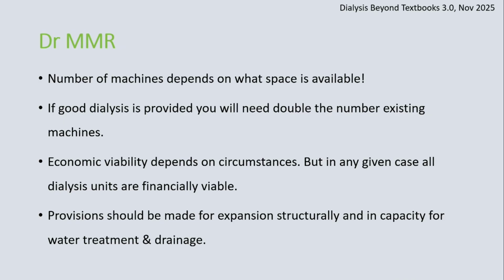Provisions to be made for expansion: when you're starting from zero, you can consider where you will expand, and you're building structural capacity. Adequate load-bearing capacity in the foundation needs to be done right at the beginning. If you start doing it next time, then you can't augment a foundation. So therefore, you should do it right at the beginning. And for all these support services that you require, water, I always built in that extra capacity for water right at the beginning, because if you want to make a new one, then it costs more. So we can aim for big and start modest and then expand.